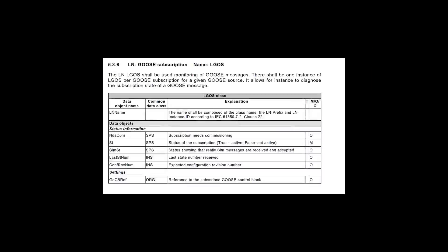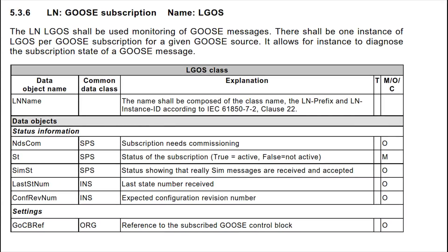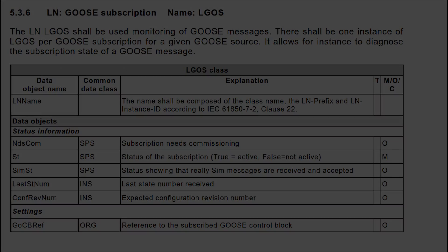As shown in this excerpt from the IEC 61850 specification, the LGOS logical node is used for monitoring Goose messages through an MMS client connection. There is a separate LGOS logical node for each subscription to a Goose publisher, which facilitates diagnosing the subscription state of Goose messages.